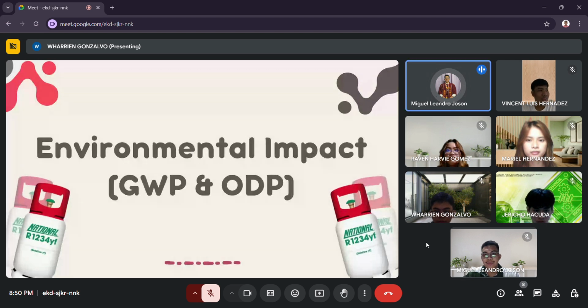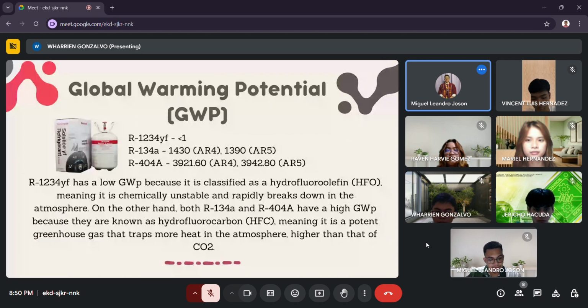Next, we move on to the environmental impact, which is the GWP and the ODP. The global warming potential, or the GWP. R-1234yf has a global warming potential rating of less than 1, while R-134a has a GWP rating of 1,430 for AR4 and 1,390 for AR5. And R-404A has a GWP rating of 3,921.60 for AR4 and 3,942.80 for AR5.